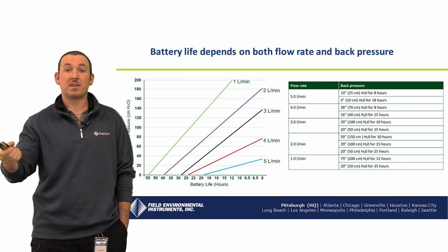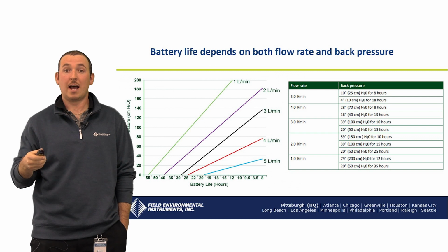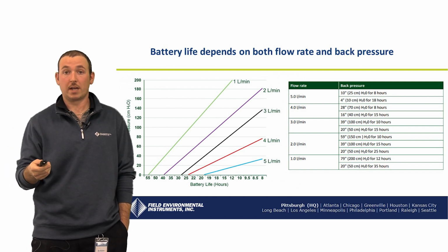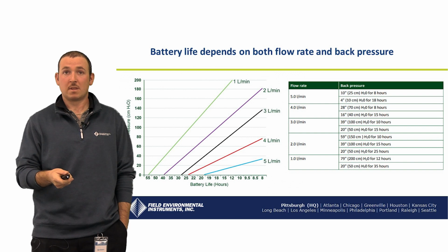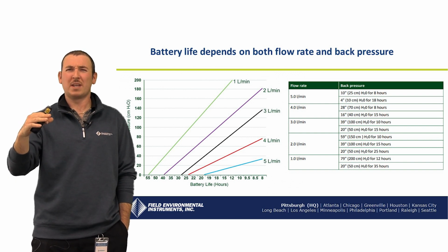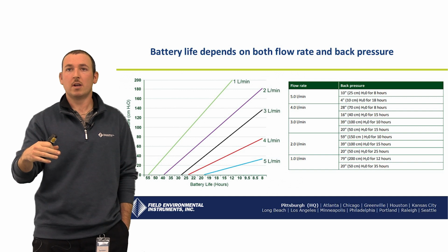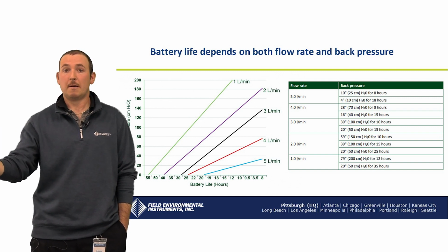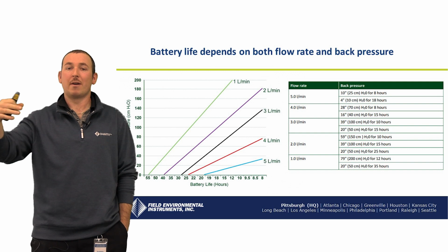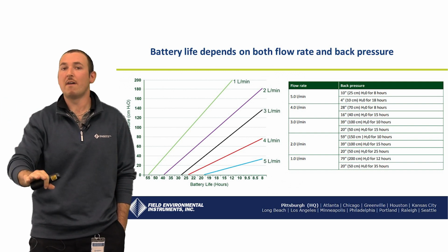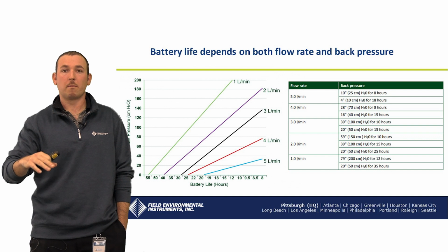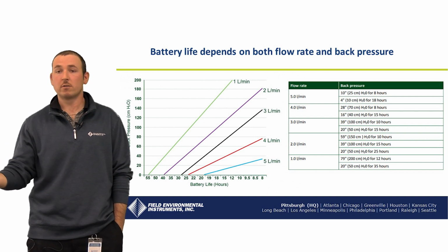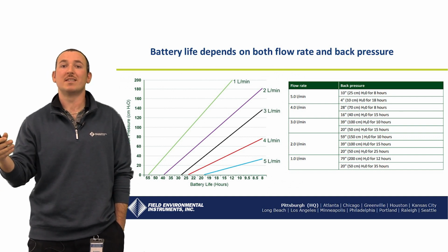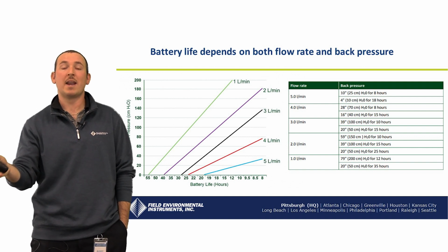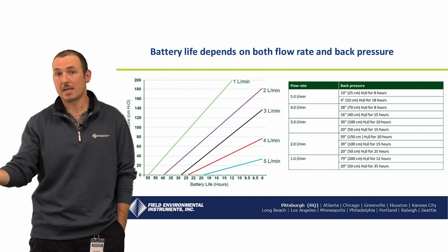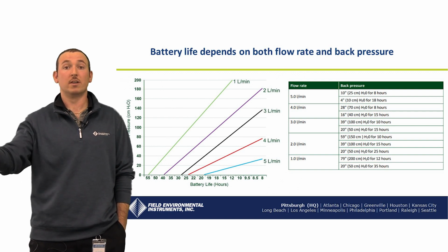But likely what you're going to see is somewhere in this range on the graph, depending on what your flow rate is. But one thing that I do want to point out is that back pressure has a huge impact on battery life when it comes to the Apex 2. As you can see on this table, when you only have about 20 inches of water in back pressure, your pump can last for 35 hours. But once you up that back pressure to about 80 inches of water, you're only looking at about 12 hours of battery life. So whenever you're planning your sample, make sure you're thinking about what filter media am I using? How long do I need this sample to last for? Because depending on those different things, depending on what your flow rate might be, you might not have enough battery to last for your entire sample.